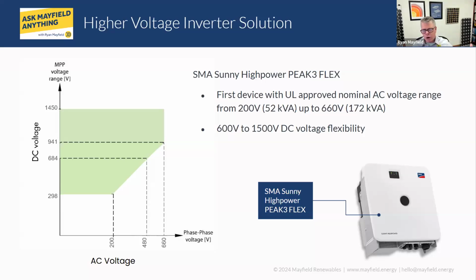All inverter manufacturers are going to have something similar to this. And so when you're replacing inverters, again, if you're trying to do that one for one, you're putting a 1,000 volt 50 kilowatt inverter in place of a 600 volt inverter, you really need to pay attention to what those operating voltage windows are and what the power output is. And so I think that's what relates here. And so Jose, I'll let you talk about the PEAK3 FLEX and how SMA is trying to approach this problem of repowering systems.